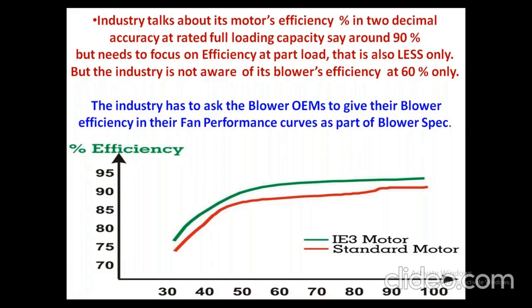Please ask the blower OEM of your mill to give the blower spec and the fan performance curve. That will show whether you are operating your blower at 60% or 50%. If you go to the HVAC side, in all the building segments, the blowers are operated at 30 to 40% efficiency. They are still operating forward curved centrifugal blowers for all these 5 HP and 7.5 HP. If this is replaced with a backward curved centrifugal impeller, it will give savings of straight away 10 to 20%.